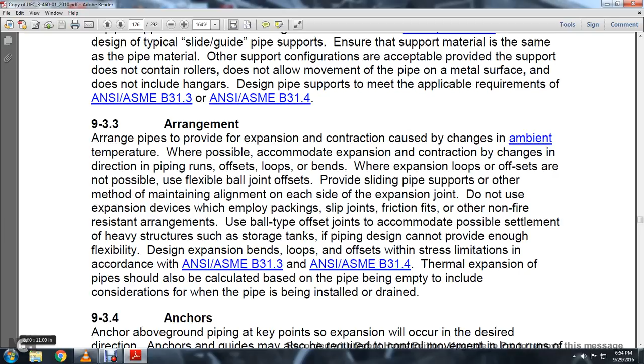If piping design cannot be provided with enough flexibility, design expansion bends, loops, and offsets with the stress limitations in accordance with ANSI ASME B31.3 and ANSI ASME B31.4. Thermal expansion of the pipe should also be calculated based on the pipe being empty, to include the consideration for the pipe being installed or drained.